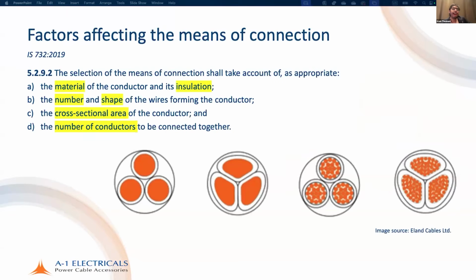Now, what are the factors affecting the means of this connection? How do you decide how you want to connect? There are a bunch of factors. Firstly, the material of the conductor and its insulation. The material, obviously, is copper, aluminum, whatever, and that is important. The insulation affects the limiting temperatures, very important again. Then the number and shape of the individual wires forming the conductor, the cross-sectional area of the conductor, and the number of conductors to be connected together. Very important things.